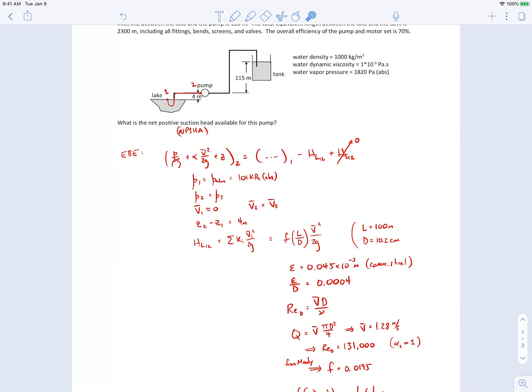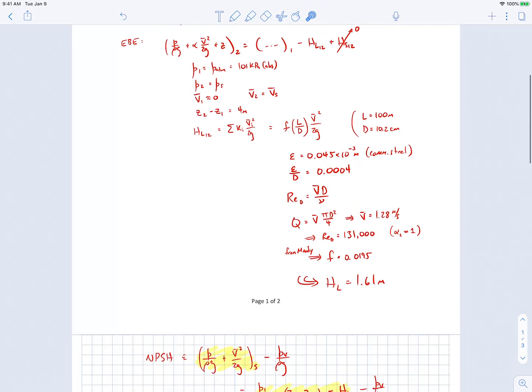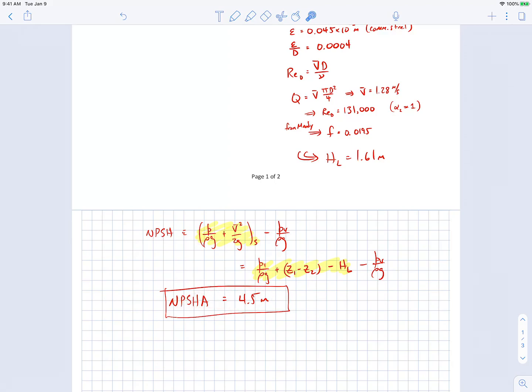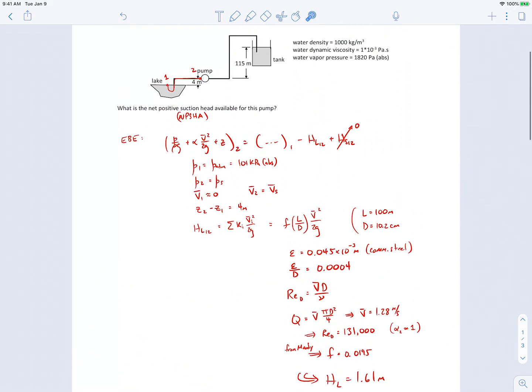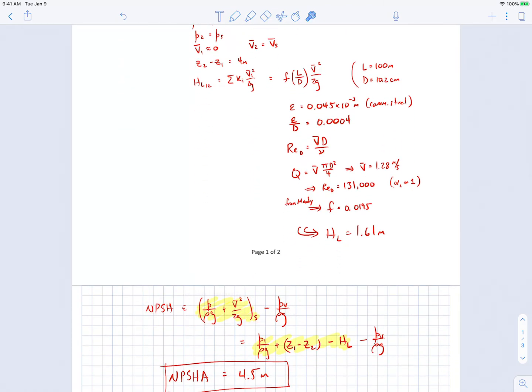The net positive suction head available to the pump is 4.5 meters. To ensure the pump does not cavitate, we need the net positive suction head required (NPSHR), which is a pump property, to be less than this NPSHA value. The NPSHA is a pipe system property calculated by applying the extended Bernoulli equation to the suction side of the pump and rearranging it to match the NPSH definition.